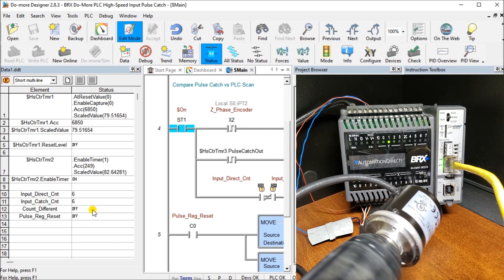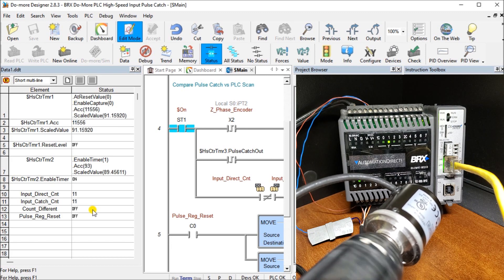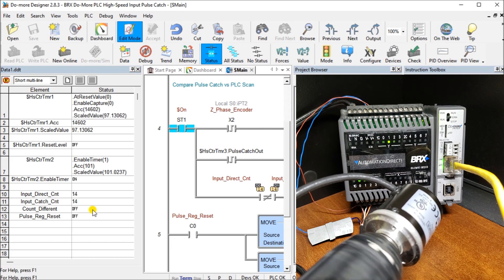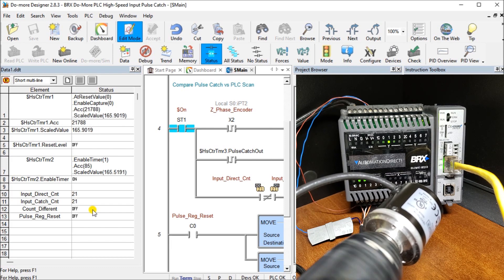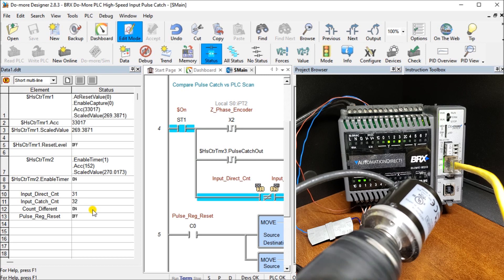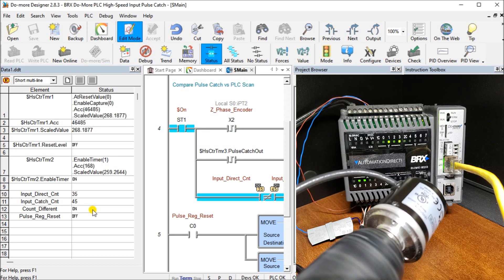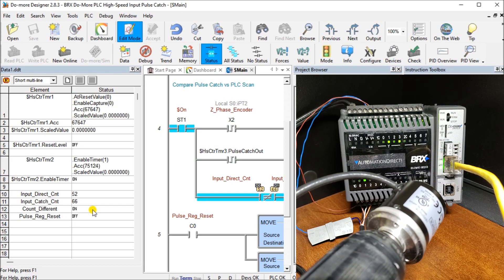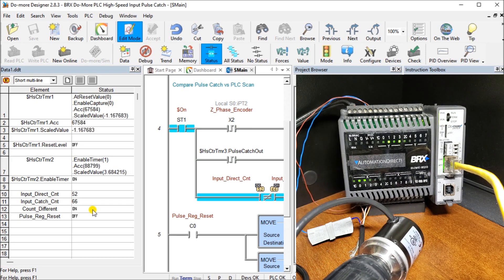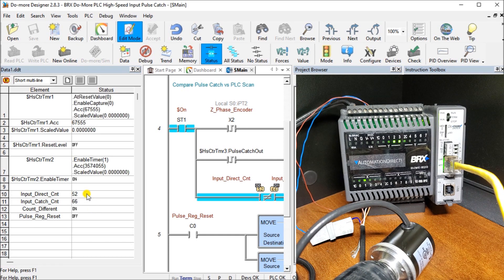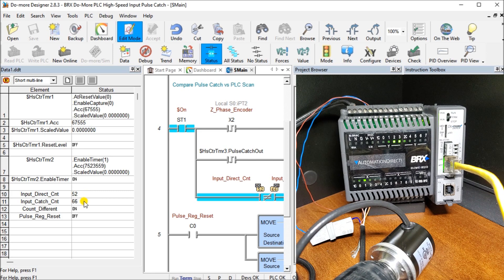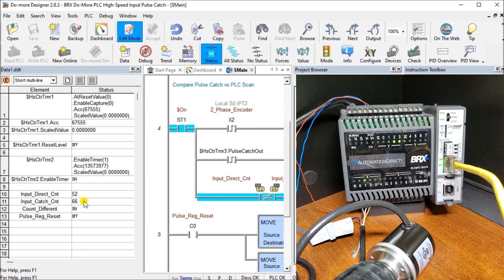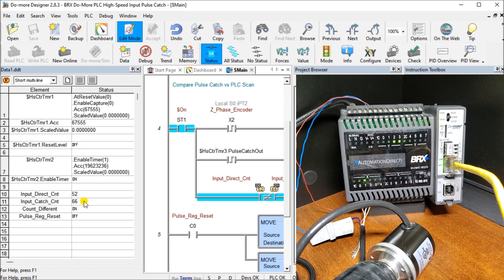But when we start increasing that speed, at one point, what you'll see is that we're going to have pulses coming in faster than what the scan time can pick up. And that will give us a large difference between the two. So we'll stop that right now. And what you'll notice is that now on our input, it only picked up 52 pulses, because it missed some of those input catches. But on our input catch pulse, on our high-speed, we have 66. So very straightforward to implement our input catch pulse bit that we can use later on in our program.